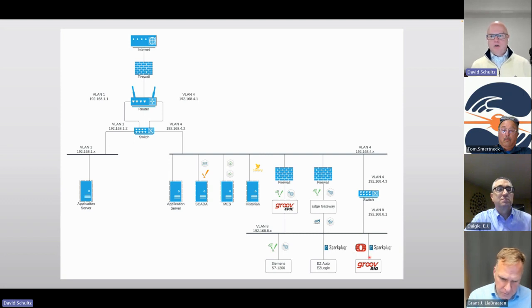Or the last piece I can use here is my groov Rio, and there's a couple ways I can get information out of it. I can either use its native Sparkplug publishing capabilities, or I can combine this Rio with my Epic, which actually has two different network cards on it. One's going to be sitting on my control side, and the other one's going to be sitting on my PLC side, so I can talk right to that PLC or talk right to that groov Rio utilizing the Opto MMP.